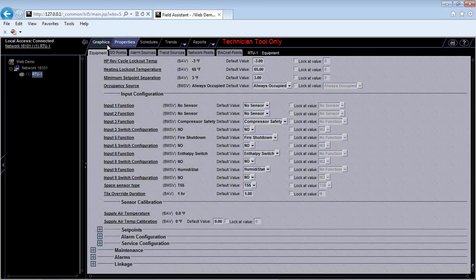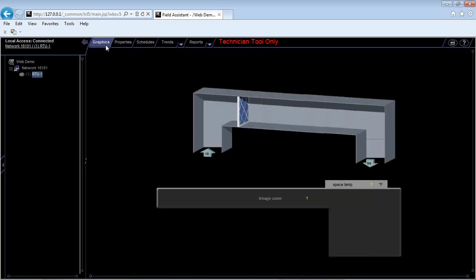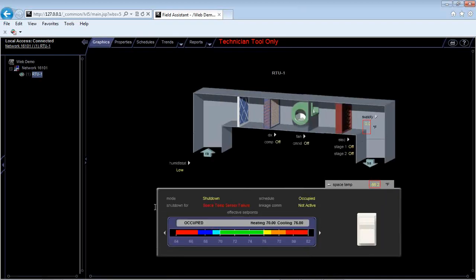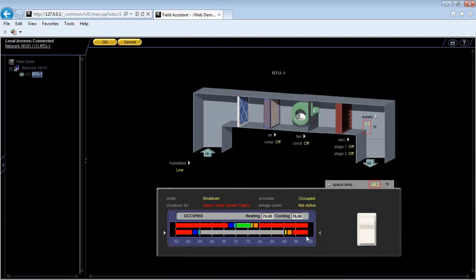We can look at it here real quick. So if I go to my graphics page, on the bottom here I have my occupied set points, so you can see I have heating and cooling of 70 and 76. If I hit this little arrow here, this allows me to type in my occupied heating set points.